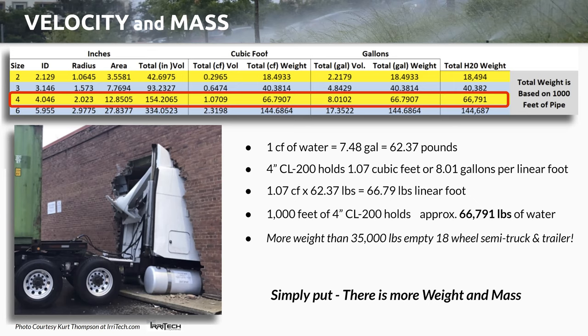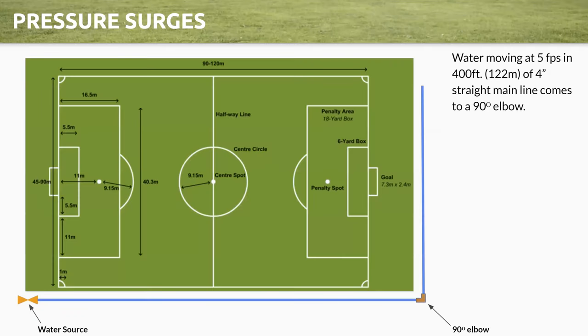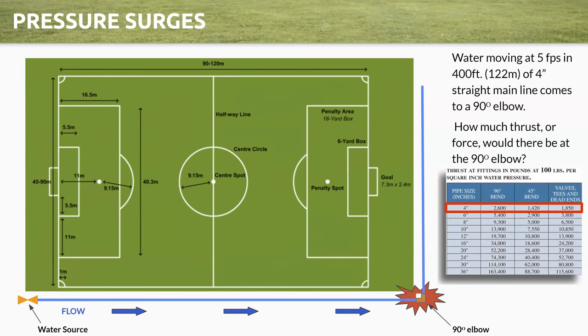So how do we relate that to, say, a soccer field? If water is moving at five feet per second on 400 feet of mainline, how much thrust is there going to be at the elbow in the lower right-hand corner? When you look at that, there are charts out there by various engineering firms, and we'll delve into this in more detail further in the webinar. But in a four-inch mainline at 100 psi, you could actually have as much as 2,600 pounds of thrust. So as you're designing and putting in these systems, you need to be able to manage these surges.